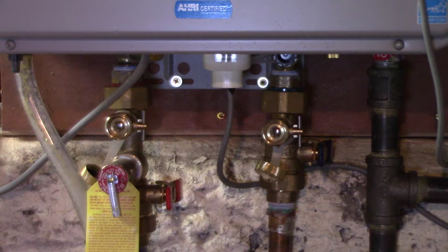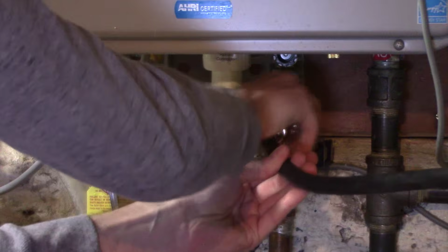Now on our service ports here, we're going to take both the caps off. If they're on too tight, you may need pliers. Now the hose that we connected to the pump, we're going to go ahead and screw that into the cold water side—this is where the vinegar solution is going to go in. Make sure you don't cross thread. Now on the hot side, we're going to take our other hose and thread it on there.